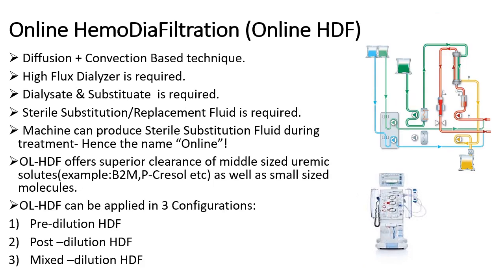The next modality is online haemodiafiltration, or online HDF. Online HDF is a combination of two solute transport mechanisms: diffusion and convection. HDF means diffusive transport plus convective transport. Just like online haemofiltration, a high flux haemodialyzer is required. Here, both solutions are required — one is the dialysate and another is the substitution fluid. The machine itself can produce sterile substitution fluid during treatment.